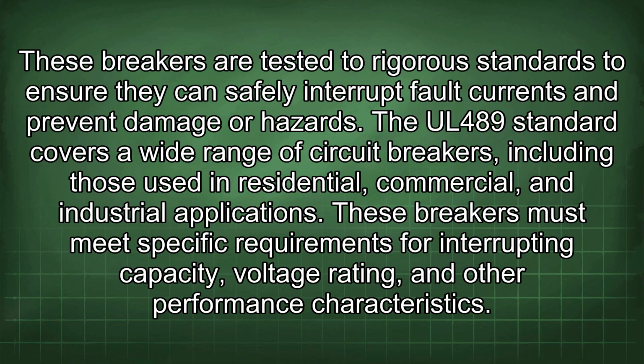These breakers are tested to rigorous standards to ensure they can safely interrupt fault currents and prevent damage or hazards. The UL 489 standard covers a wide range of circuit breakers, including those used in residential, commercial, and industrial applications. These breakers must meet specific requirements for interrupting capacity, voltage rating, and other performance characteristics.